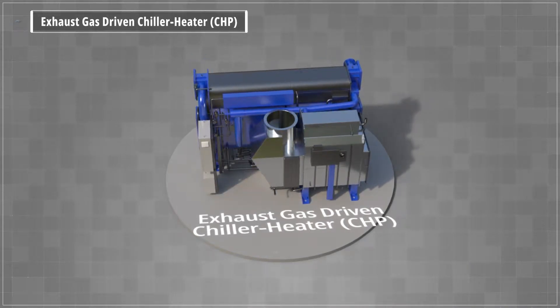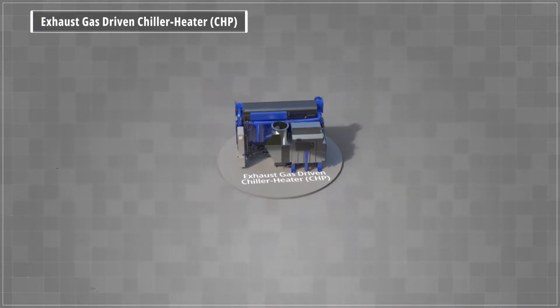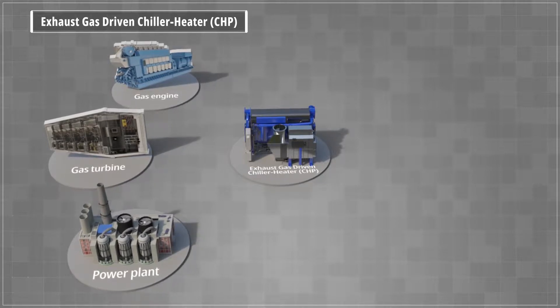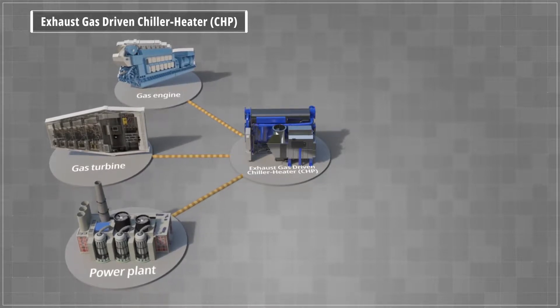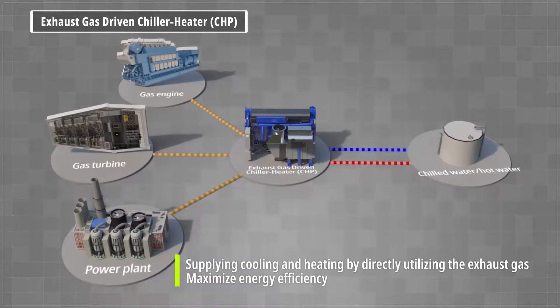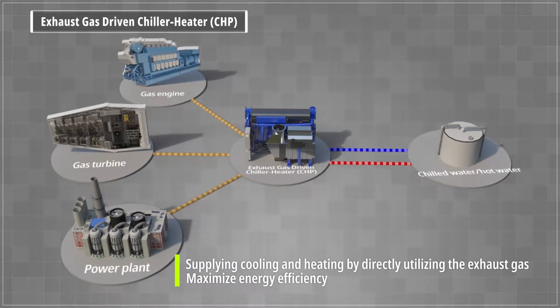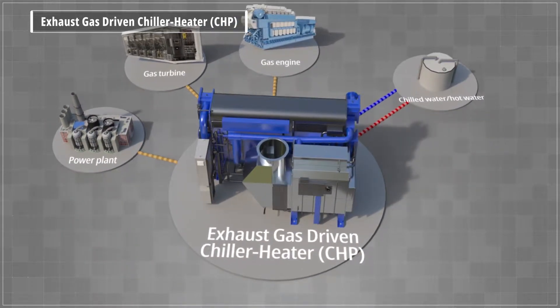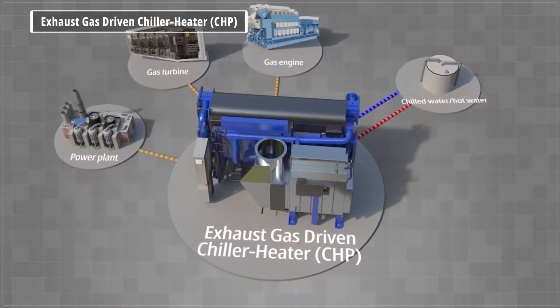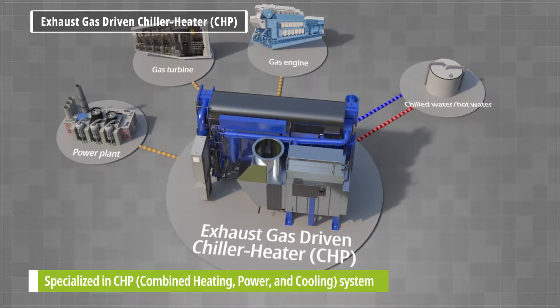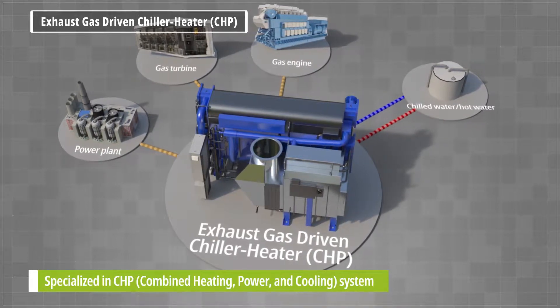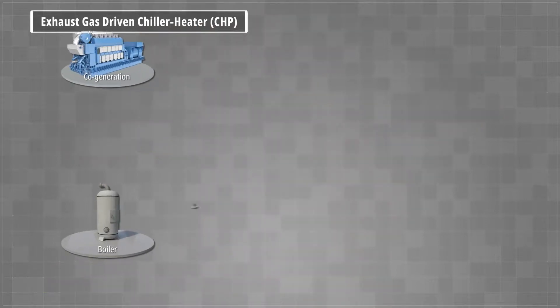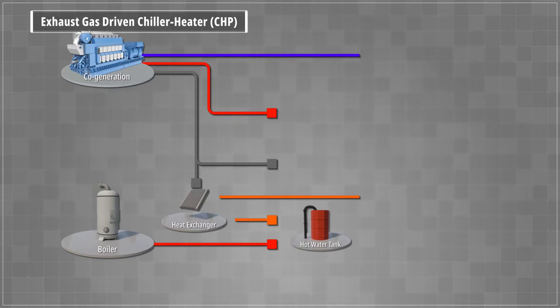World Energy's Exhaust Gas Driven Absorption Chiller and Heater, also referred to as CHP type, utilizes exhaust gas from an incinerator or gas turbine to generate cooling and heating. Direct recovery of the exhaust gas with minimal loss maximizes energy efficiency. CHP series are supplied to combined heat and power generation facilities, where CHP and HWARL units are used together.